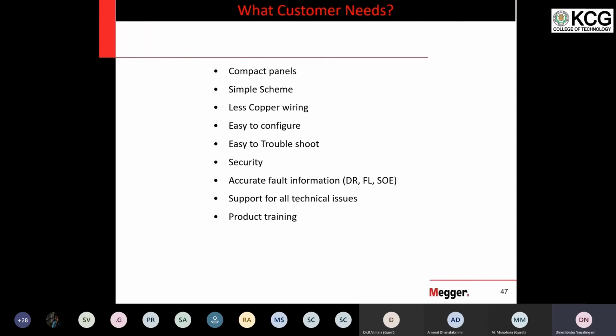However, currently the relay will trip, but in addition, it gives these things: DR, FL, SOE. DR means disturbance recorder. FL means fault locator. SOE means sequence of events. With these three informations together, you will get accurate information. So what does that mean? When the relay trips, it says that 40 kilometers from our substation, in R phase, the jumper is broken. Just imagine if a relay is giving you this information, how fast you can restore the system.